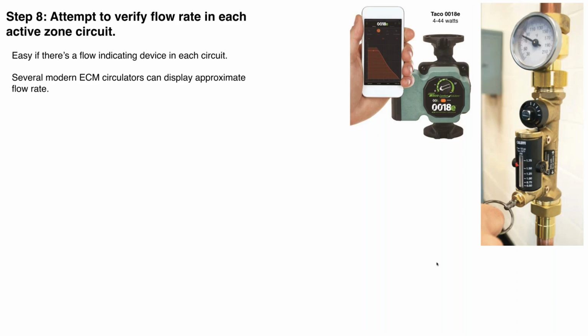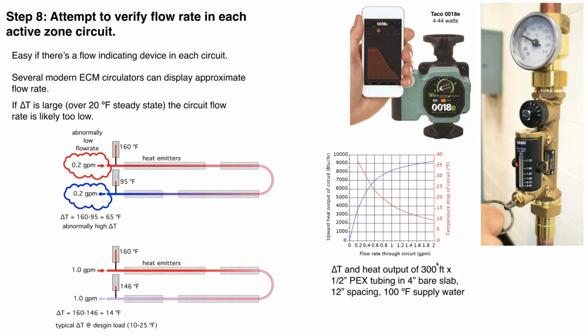If you're expecting 6 gallons a minute and you're seeing 2 gallons a minute, obviously there's something inhibiting that flow. If you're seeing 5.5 or 6.5, that could be within the tolerance of the measuring device. But I do appreciate the fact that these circulators can at least give you a reasonable estimate of what that circuit flow rate is. Here's another thing. When you see very large temperature drops in a circuit, it's almost always an indication that the flow rate is too low. So up here at the top, here's a case where we have a tiny little flow rate going in here.